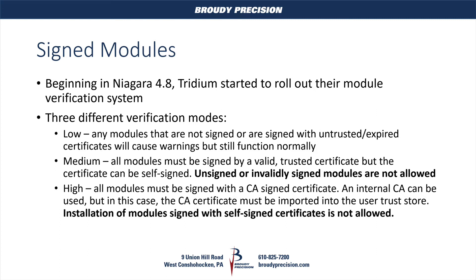In low mode, you could go into your application director and see a warning about the certificate not being there or the code not being signed, but the code will still run and your module will still operate as it's supposed to. With medium, all the modules must be signed with a valid, trusted certificate, but they can be self-signed. Unsigned or invalidly signed modules are not allowed, and you will not be able to open or run the code in them at all.